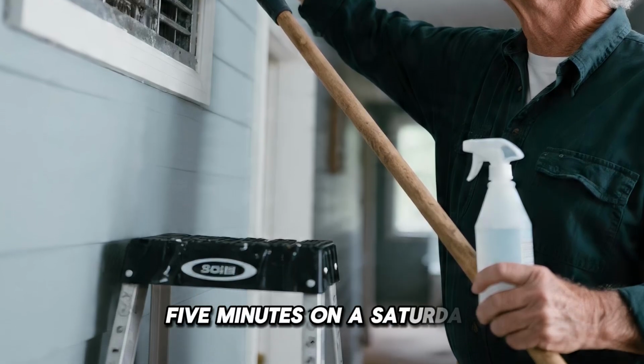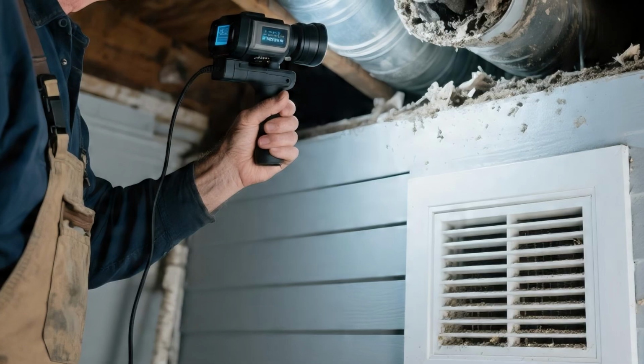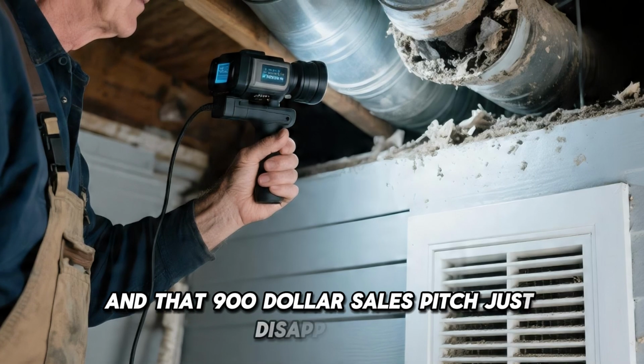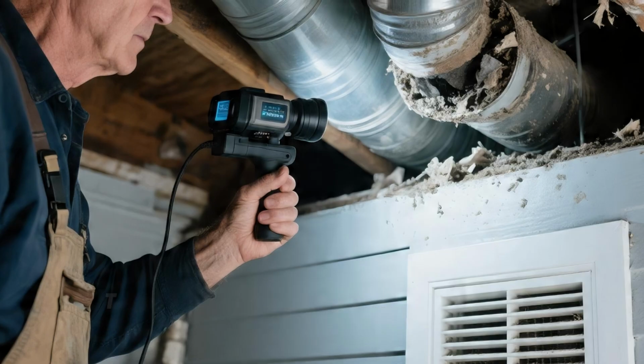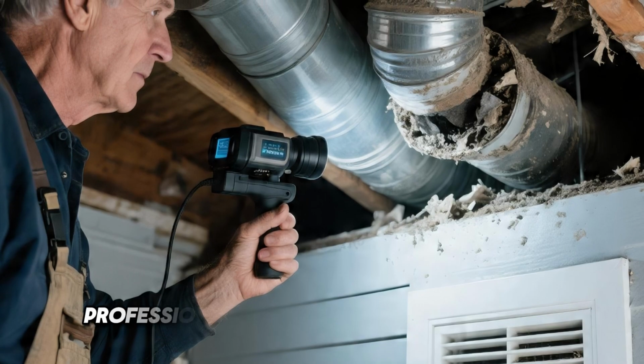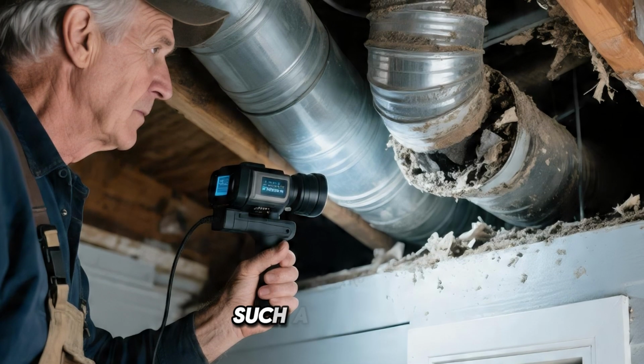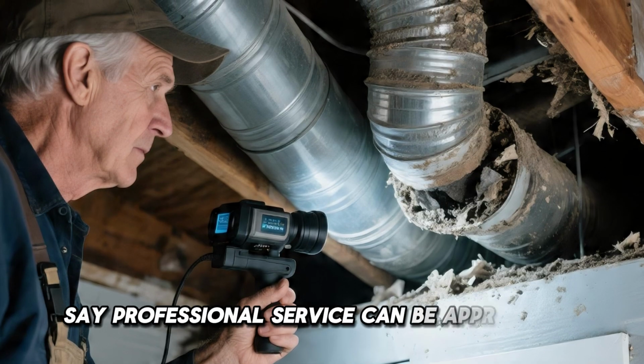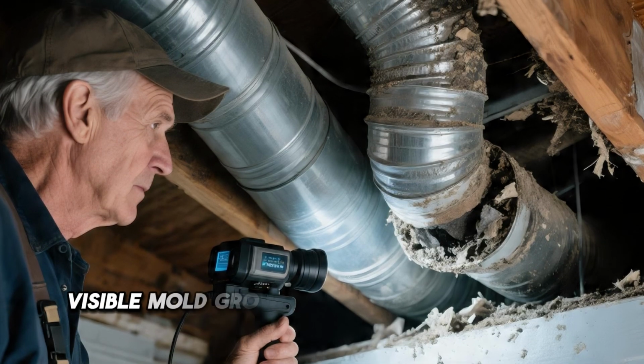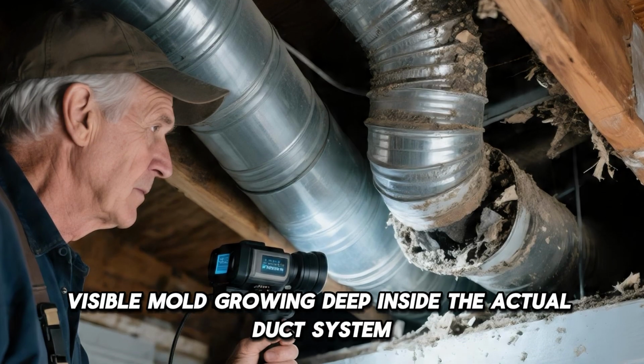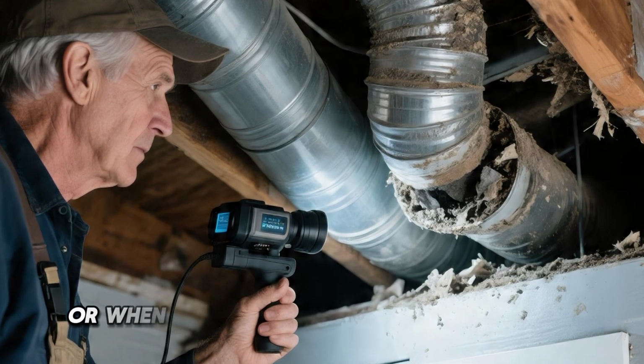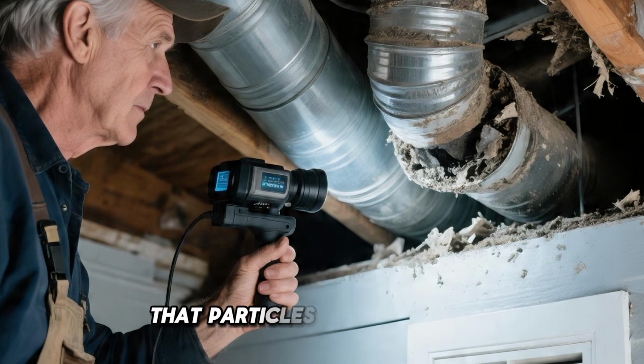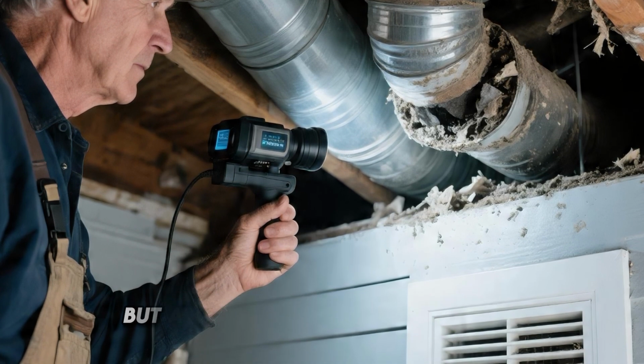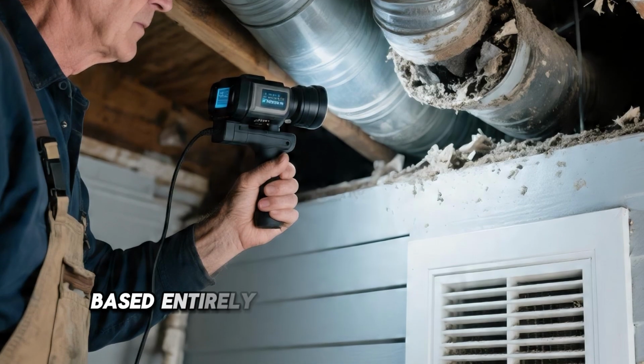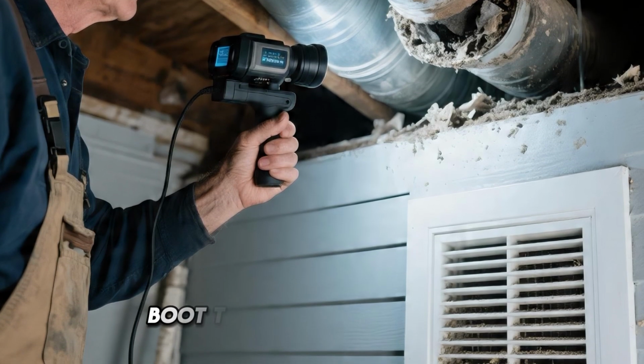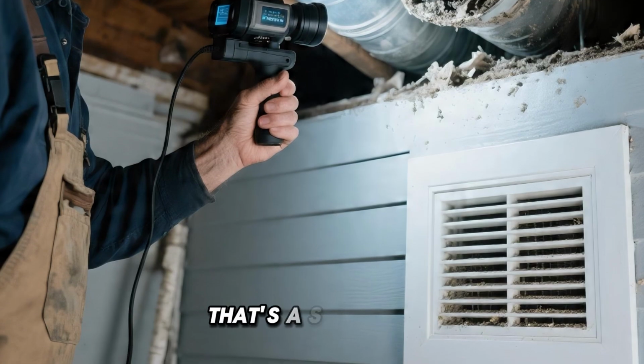5 minutes on a Saturday. About 30 cents worth of peroxide. And that $900 sales pitch just disappeared. Now, to be fair, there are legitimate reasons to have ductwork professionally cleaned. Federal agencies such as the EPA say professional service can be appropriate when there is substantial visible mold growing deep inside the actual duct system, when vermin have infested the ducts, or when debris has accumulated so heavily that particles are physically blowing from the registers. But a $900 recommendation based entirely on one photograph of a sweaty register boot? That's not an inspection. That's a sales pitch.